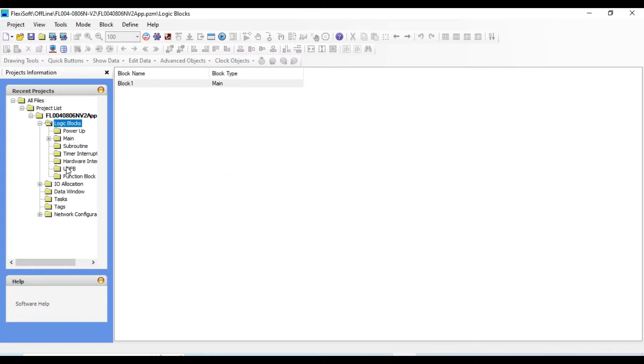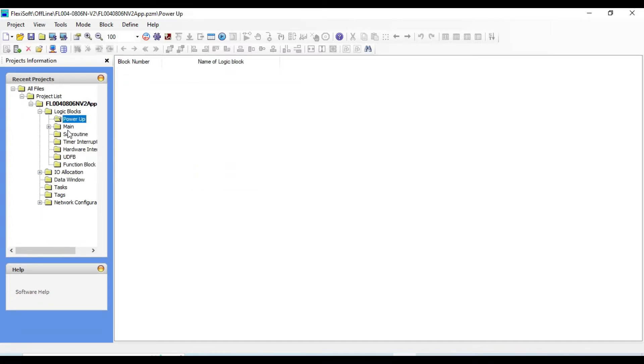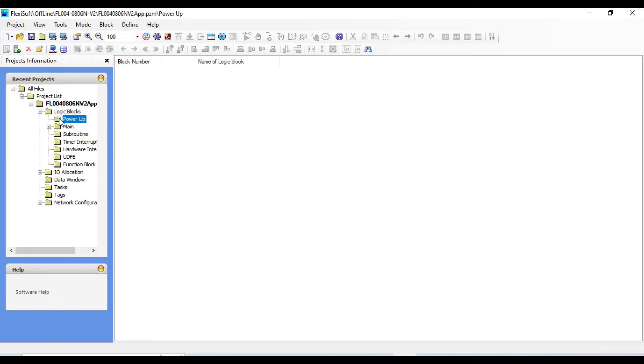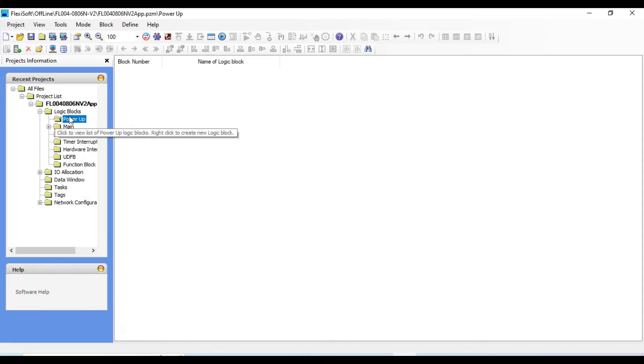Power up program is executed once at the start of the first scan. It means before the main program is executed. Therefore this program can be used to set the initial value for the registers. This is also called the initial program.